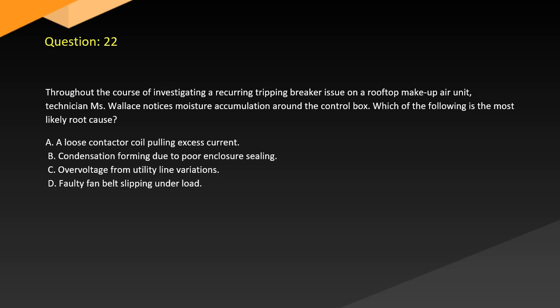Question 22. Throughout the course of investigating a recurring tripping breaker issue on a rooftop makeup air unit, technician Wallace notices moisture accumulation around the control box. Which of the following is the most likely root cause? A. A loose contactor coil pulling excess current. B. Condensation forming due to poor enclosure sealing. C. Overvoltage from utility line variations. D. Faulty fan belt slipping under load.